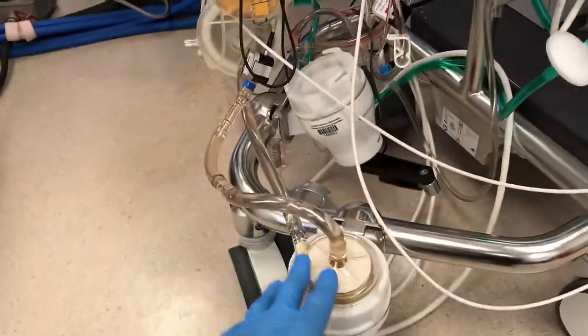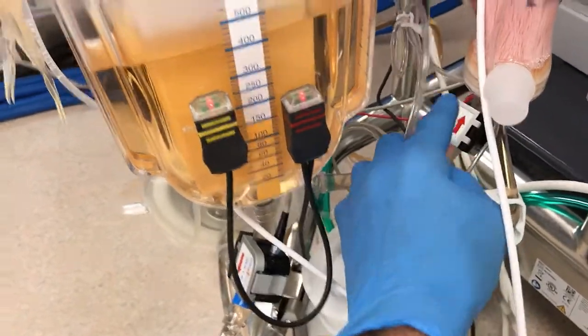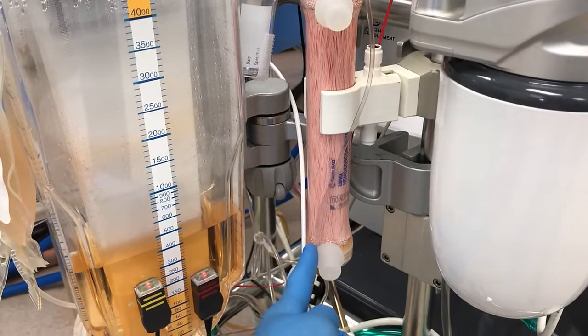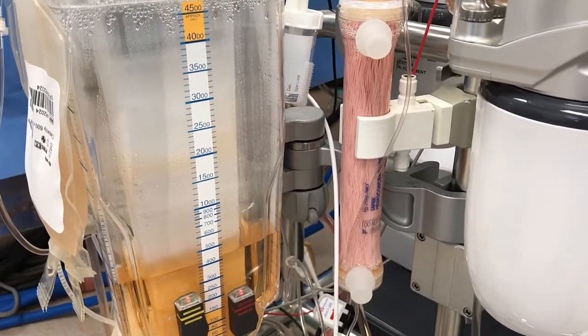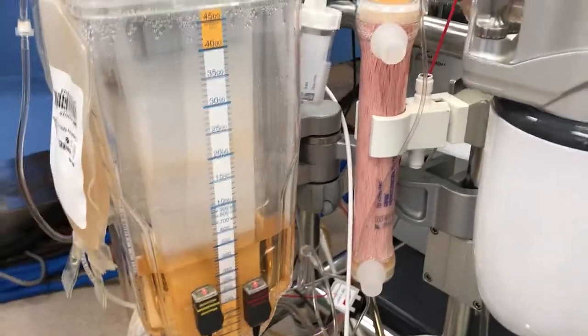So this pump is the artificial heart. This oxygenator is the artificial lung. We pump blue venous blood into this oxygenator. It comes out the other side, it would be red. Red arterial blood would go back up into the patient. As long as we're here, this is an artificial kidney of sorts. This is a hemoconcentrator. We use that when we want to change the volume status of the patient. So we have artificial hearts, artificial lungs, artificial kidneys as part of our extracorporeal technology.